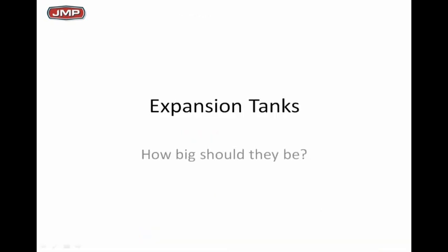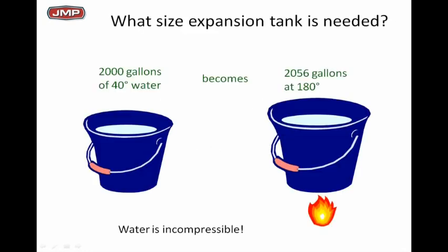So let's talk a little bit about expansion tanks. How big should they be? How big a tank do you need? Now, obviously, going back to our example of expansion, water is incompressible. I've got 56 gallons of water I've got to do something with. And hopefully we put it in the expansion tank. That's what the goal would be.